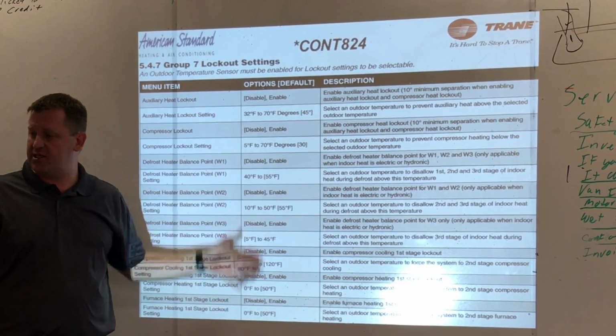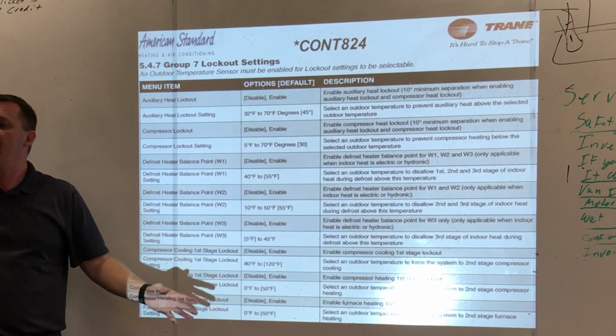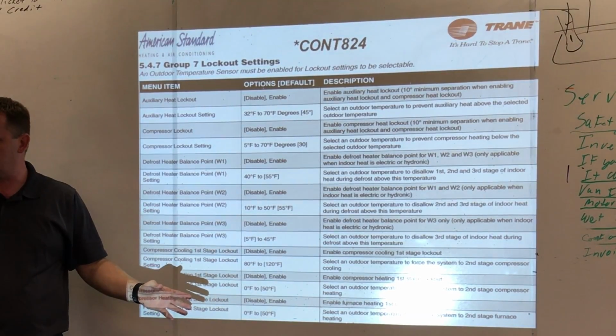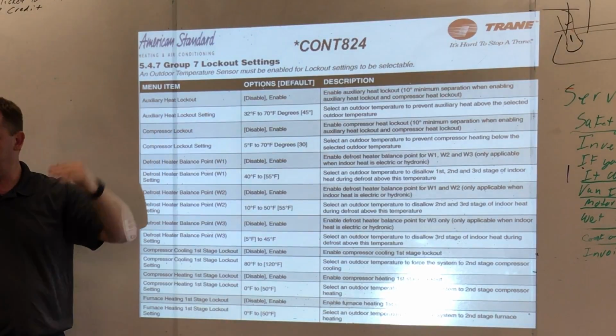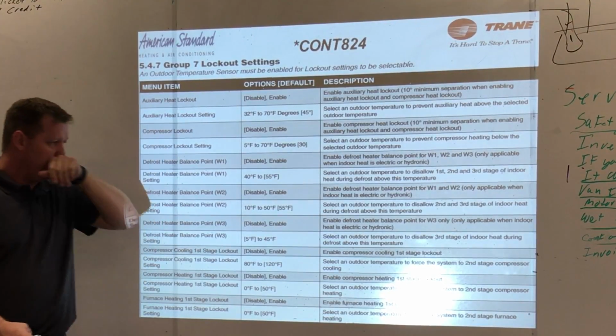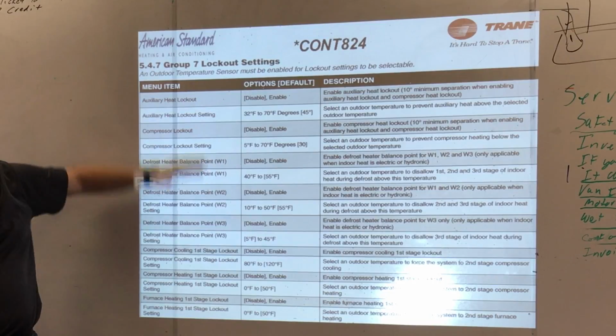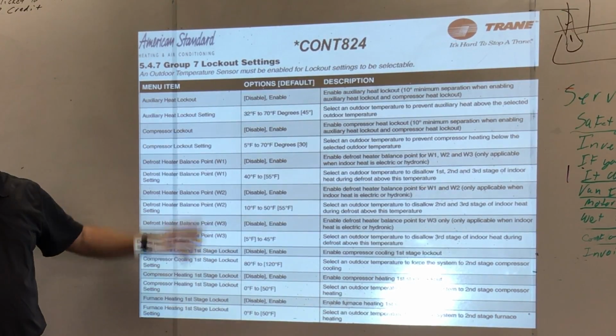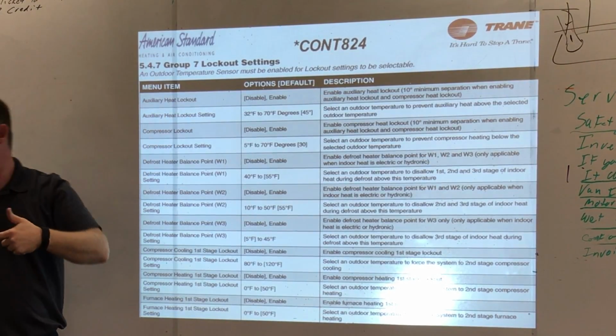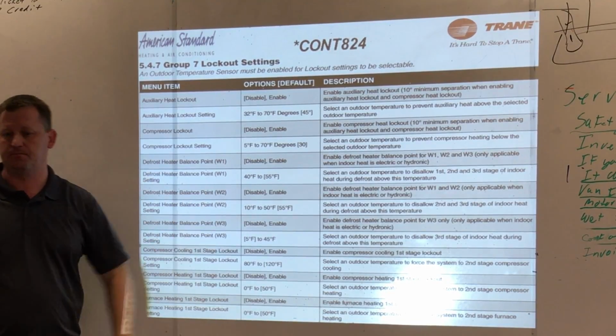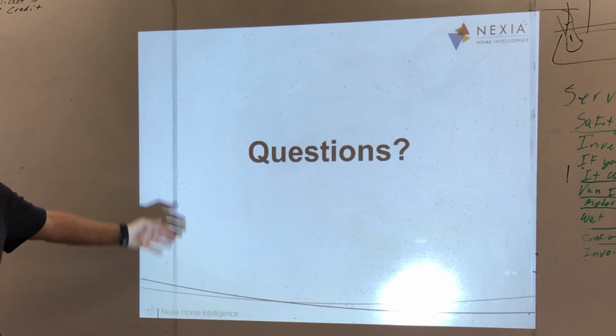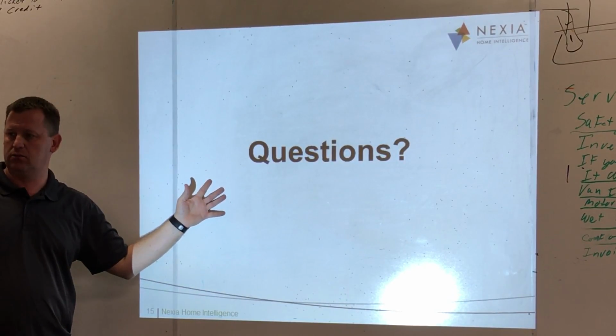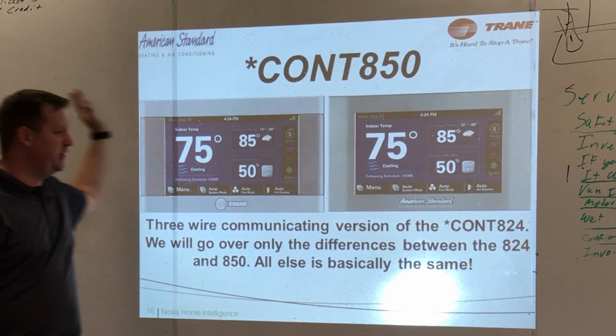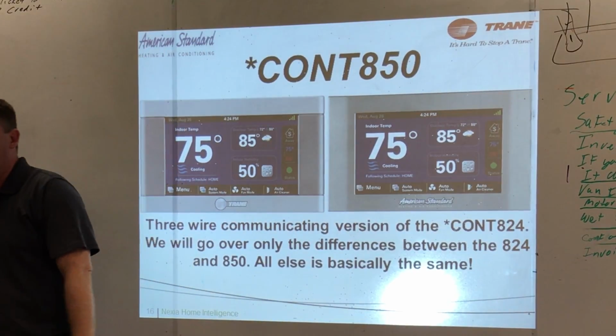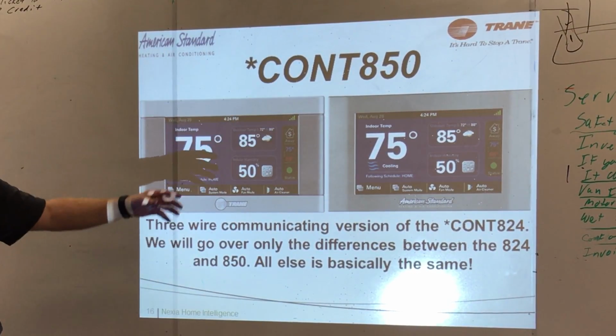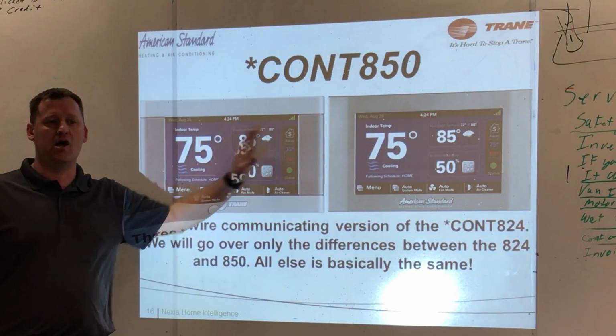Now, you won't have these settings unless you put an outdoor sensor on and tell it that it has an outdoor temp sensor. Again, it's discovery setup, so if you didn't set up an outdoor temp, you don't get any of this, including auxiliary lockout, which for PTCS they have to have. So, any other questions on the 824? Okay, the 850 is exactly the same as the 824 except that it's communicating. Really, that's the difference between these two. Functionally, the homeowner cannot tell the difference.